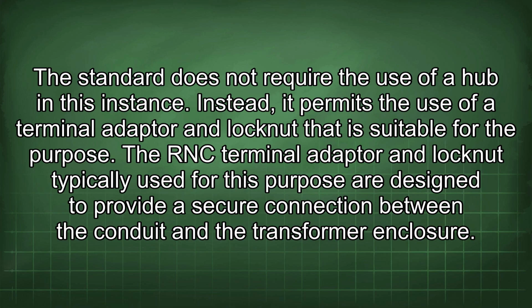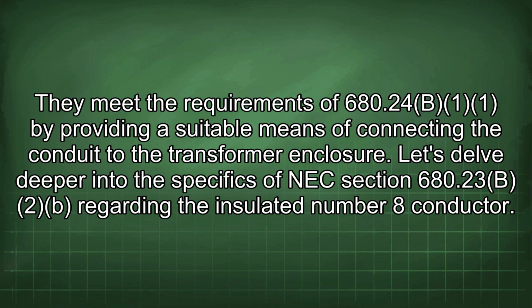The RNC terminal adapter and lock nut typically used for this purpose are designed to provide a secure connection between the conduit and the transformer enclosure. They meet the requirements of 680.24(B) by providing a suitable means of connecting the conduit to the transformer enclosure. Let's delve deeper into the specifics of NEC Section 680.23(B)(2) regarding the insulated number 8 conductor.